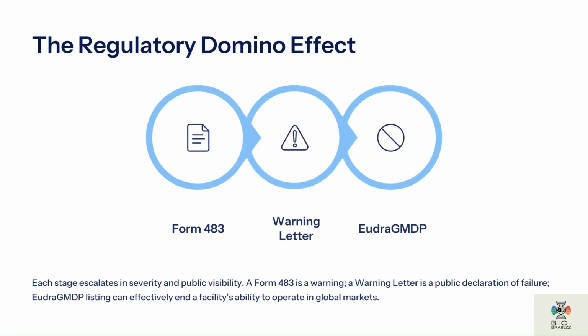Regulatory actions usually happen in stages. First, inspectors may issue a Form 483. This means observations were found during inspection. If the organization does not correct these issues, the next step may be a warning letter. A warning letter is more serious and becomes public information.